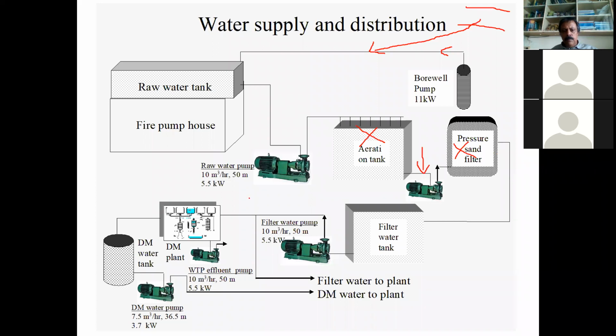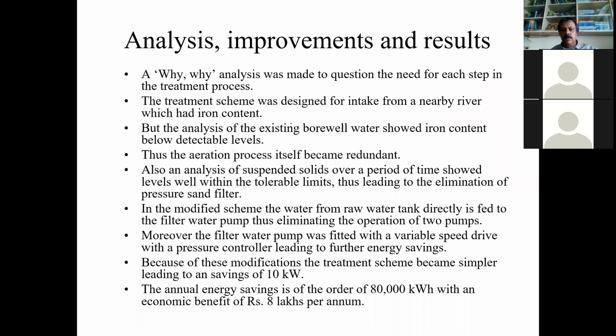Now, in many cases we find that something which started maybe several years back continues to be operated without the functional requirement or the functional need. By doing this reassessment and re-engineering of the system, these two pumps were totally avoided. So it is a very simple case. You don't need to make any major changes except for minimum piping.